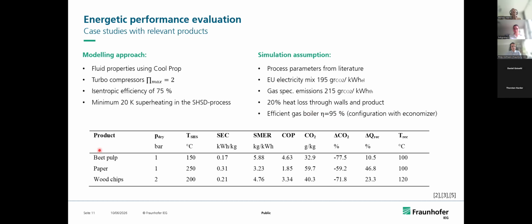For these processes with different temperature ranges, beet pulp, food, paper, in this case tissue due to the high temperature, and wood chips, we see significant CO2 reduction is always possible, even with a comparatively low COP. Here that means a 1 bar drying atmosphere with a lift of about 130 to 150 degrees, or adding to the pinch requirements in the heat exchanger. So this is a very high lift application.